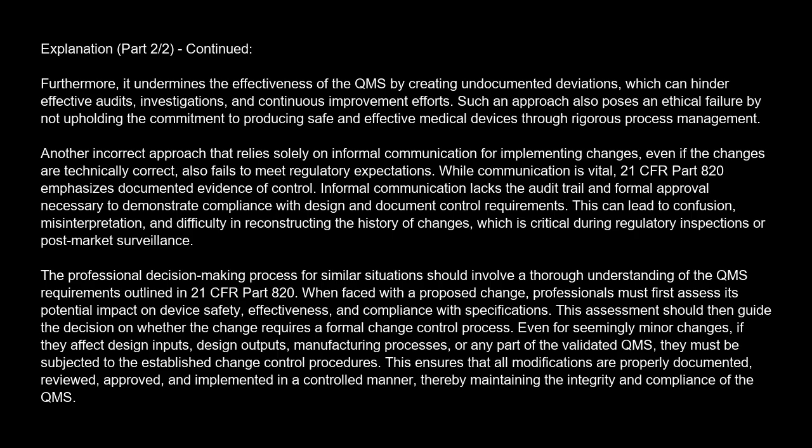Another incorrect approach that relies solely on informal communication for implementing changes, even if the changes are technically correct, also fails to meet regulatory expectations. While communication is vital, 21 CFR Part 820 emphasizes documented evidence of control. Informal communication lacks the audit trail and formal approval necessary to demonstrate compliance with design and document control requirements.